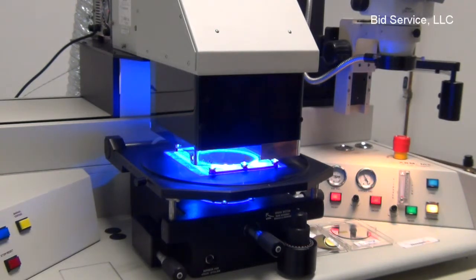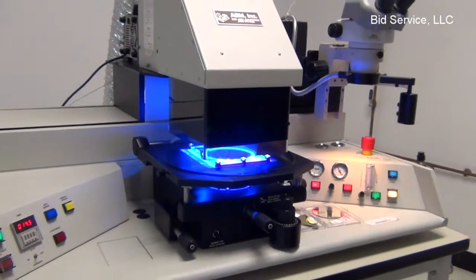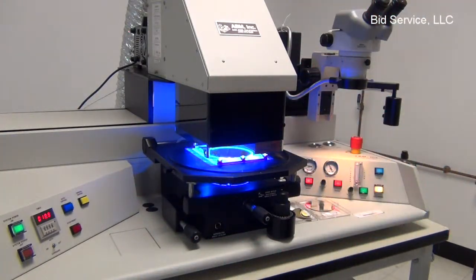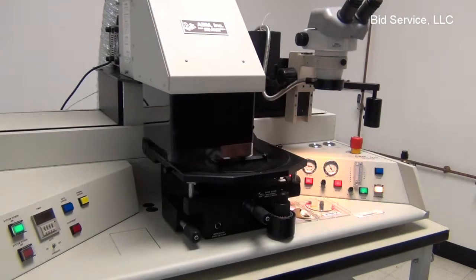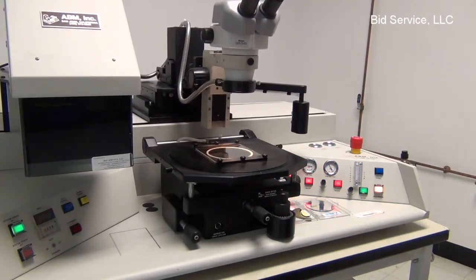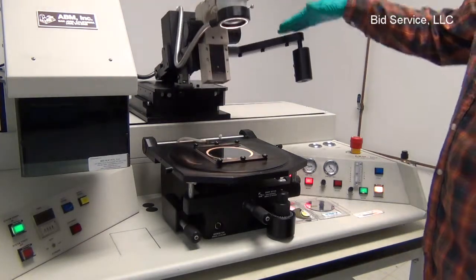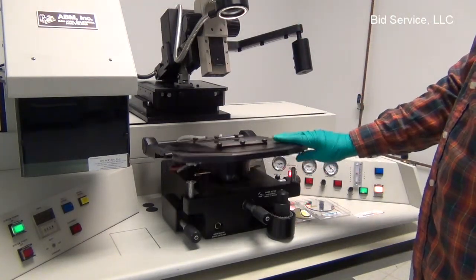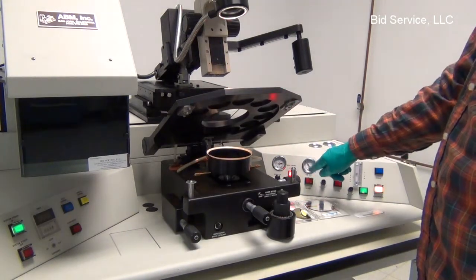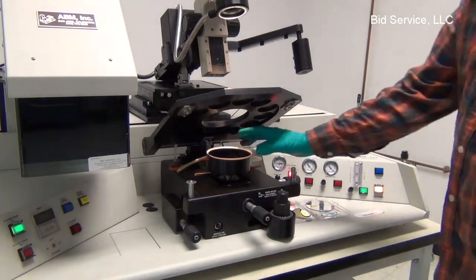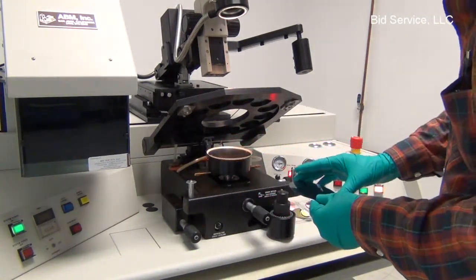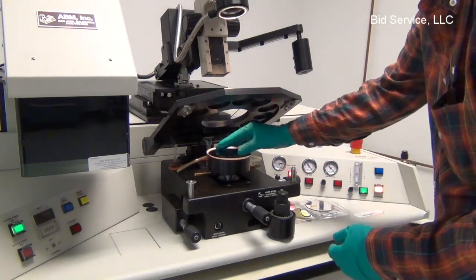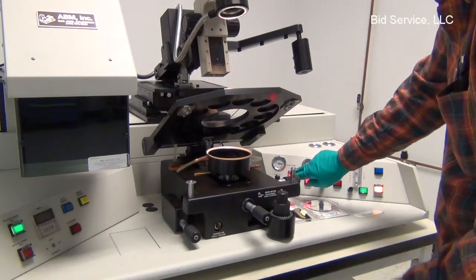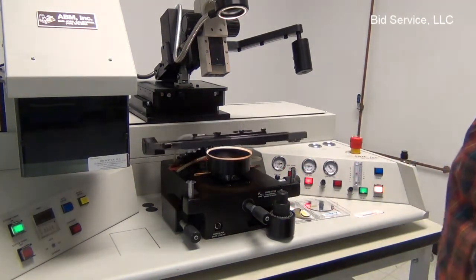The exposure time is controlled by the Omron timer, which can be set from 0 to 999 seconds. There is also a manual expose button. By pressing that, the shutter could be manually opened or closed. Once the exposure is finished, the microscope will lift up and the mask frame will rise, and the vacuum under the substrate will be turned off. To repeat the cycle again, replace the sample, turn on the substrate vacuum, and lower the mask frame again.